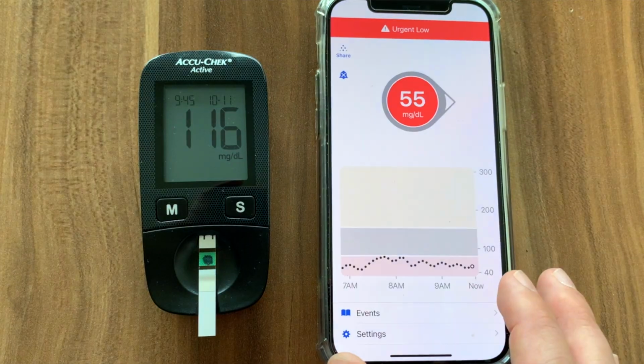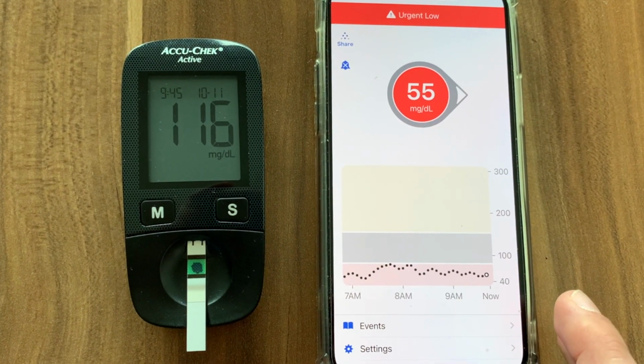Here are a few tips for a successful sensor calibration that worked for me. Tip number 1: never calibrate during the first 24 hours, because the readings during the first day, and especially during the first 6 to 8 hours when I have a new sensor on, are way off. It's not ideal, I know, but if you calibrate the sensor during these first few hours, you will mess things up. Trust me, I've been there. You might even break the sensor because it will get into a calibration loop and never recover. So don't calibrate during the first few hours.